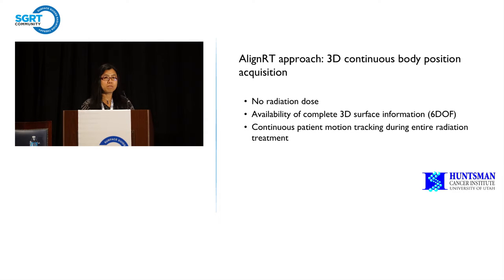Most of the other techniques either just take a snapshot, or use several marker positions, so it's not like the whole surface. The other good part is the continuous tracking. I can track the patient during the entire treatment, so whether it's 10 minutes or 1 hour, you can have the continuous patient body position.